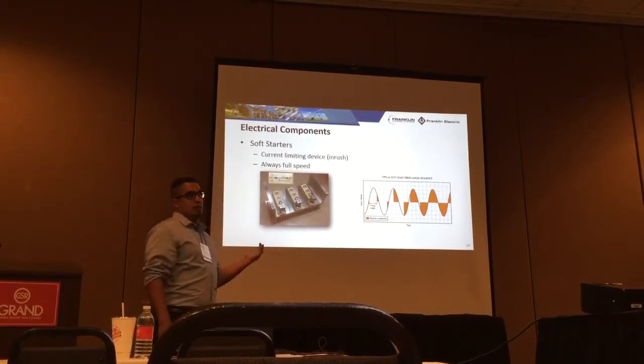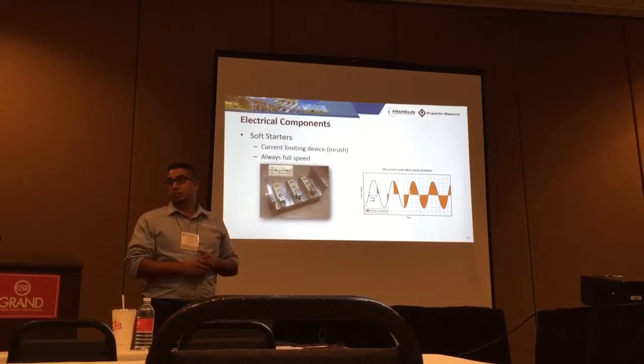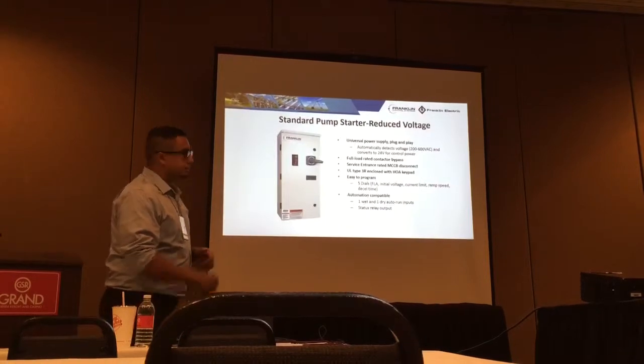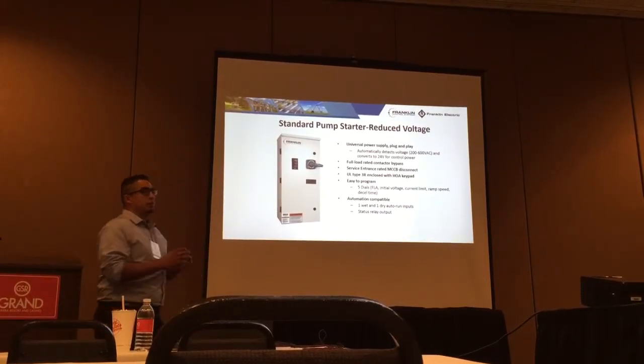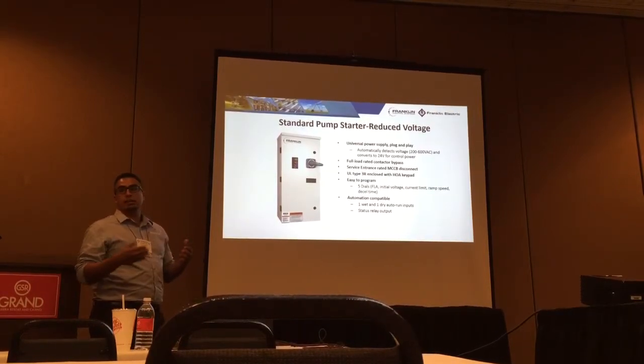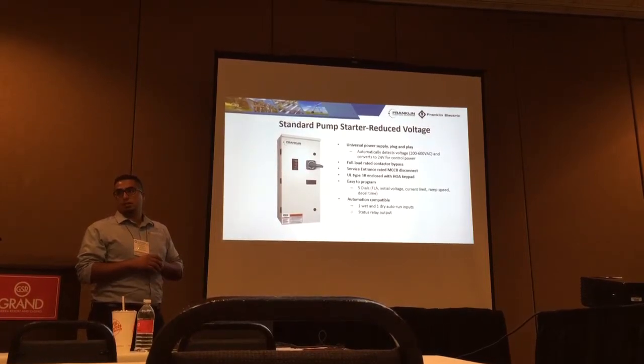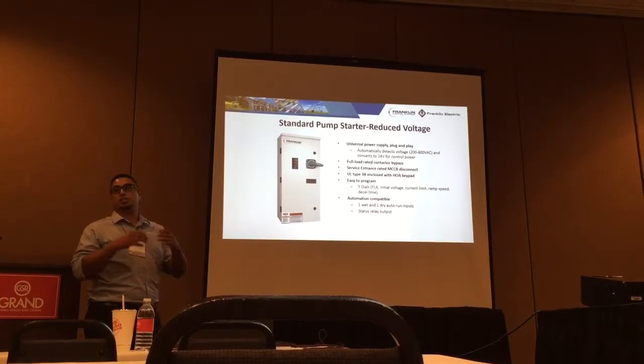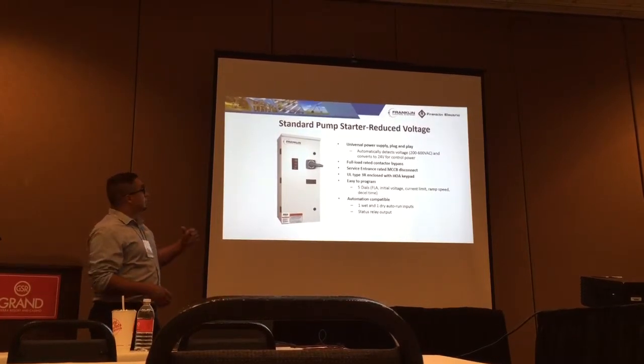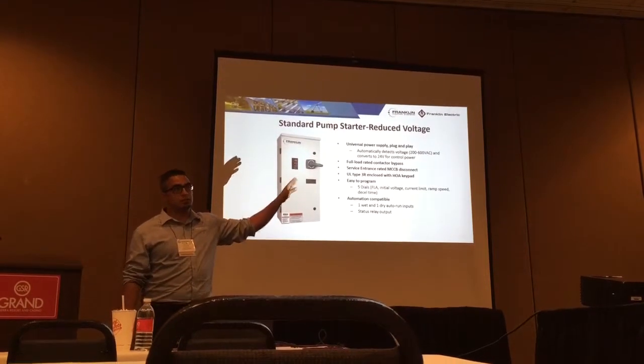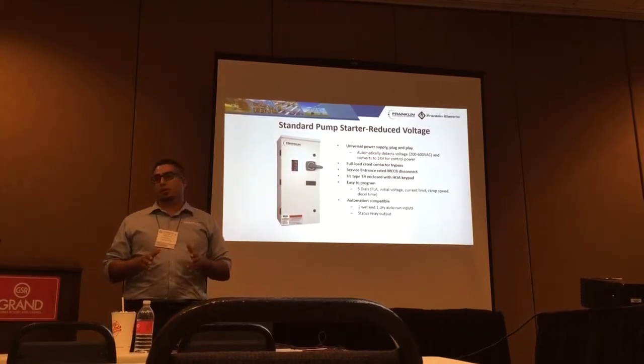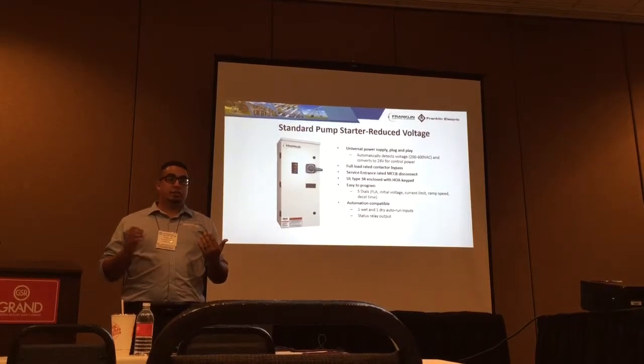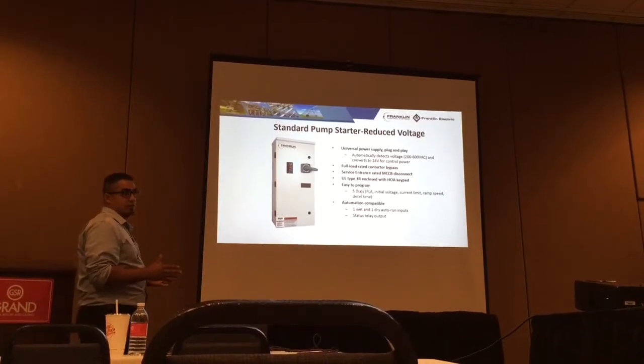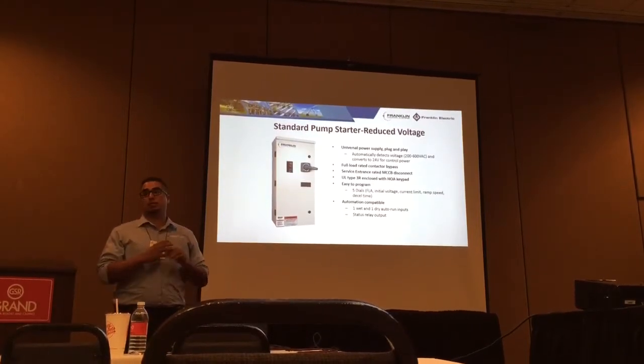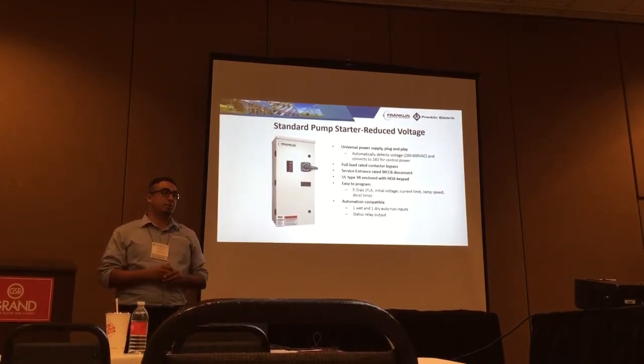But current limiting devices, back to electronic stuff, they have to be protected as well. So with these soft starts that FCS has manufactured, the whole mentality, back to what exactly are we starting again, is that they've been geared towards pump and motor starts. Higher torques out of the box, and the default settings are there to make sure that a submersible motor is up and running in 2 seconds. Automatic voltage detection, again, streamlines installation: dropping in your 3-phase power, dropping in your 3-phase motor, giving it the pressure switch run, and hitting it auto. That's the intent of where these panels need to go. Yet still providing you with that extended warranty because we know the protection's there in that panel.